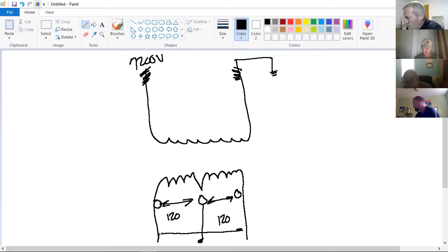This goes to neutral and grounded. I've got 120 from these two points, I've got 120 from these two points, but the combined of these two is 240. Well, Professor Shoemaker, we just got finished talking about Y, and two different phases of secondary, I told you, equals what? 208, right? How am I getting 240 volts out of this transformer?